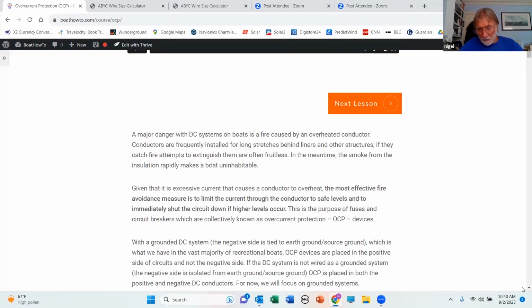People tend to think that a fuse or a circuit breaker is in the circuit to protect the equipment in the circuit. It's got nothing to do with equipment protection. The sole purpose of the fuses and circuit breakers on our boats is to make sure that if we get an overcurrent situation where we've exceeded the ampacity, the amp rating of the conductor, and now the conductor is getting hot enough to melt its insulation, that fuse or circuit breaker shuts the circuit down before we get there.